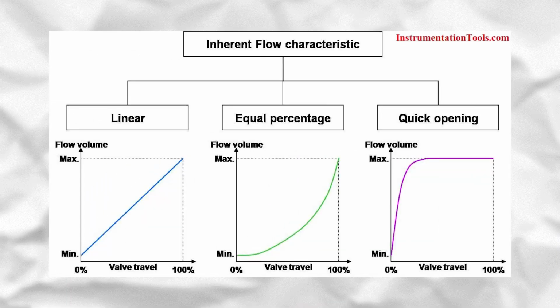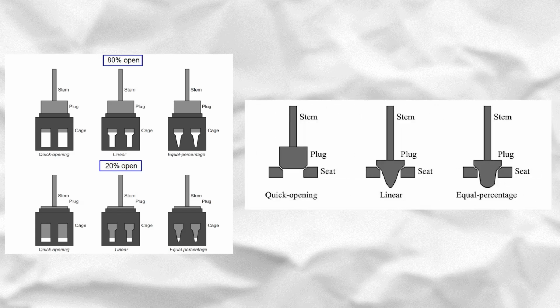Not only is the cage really helpful in noise reduction, but it can also specify the valve characteristics, whether it is linear, equal percentage, or quick opening. With the help of different cage shapes or seat and plug forms, a desired valve characteristic is made. An instrument engineer must have enough knowledge to calculate the CV coefficient of a control valve. To do so, some software is applied such as ConVal, InstruCalc, and so forth. The greater the CV, the greater the valve size and capacity.